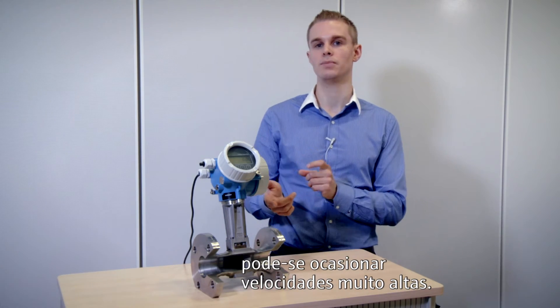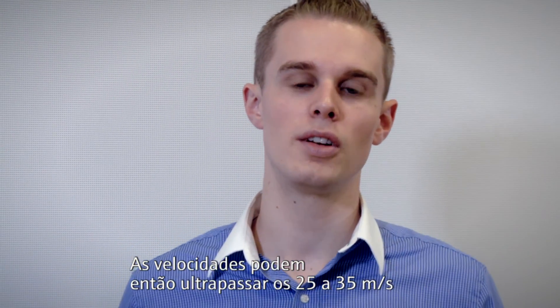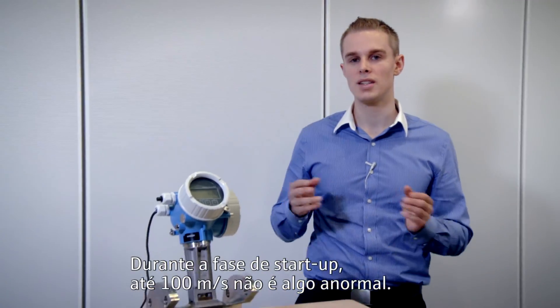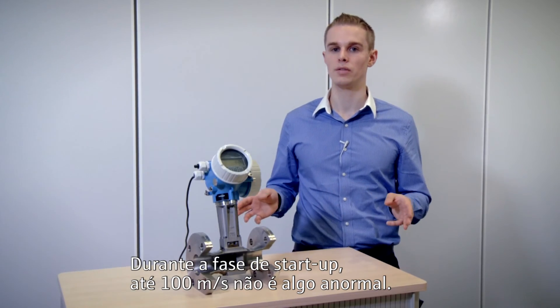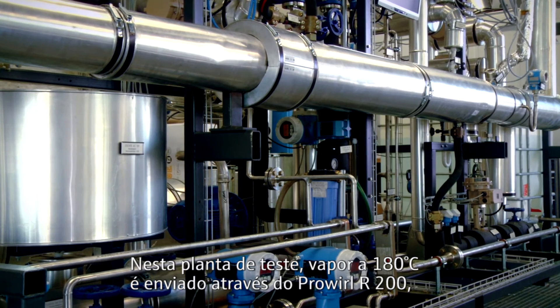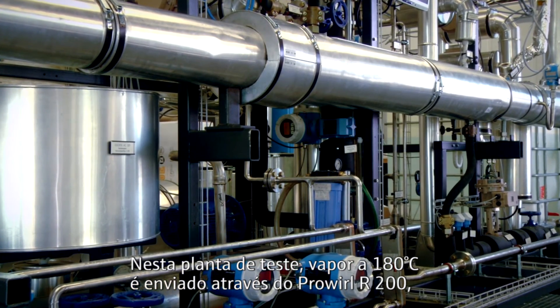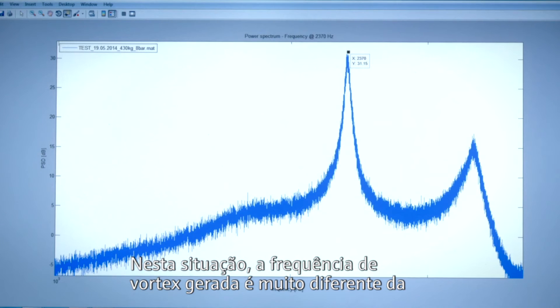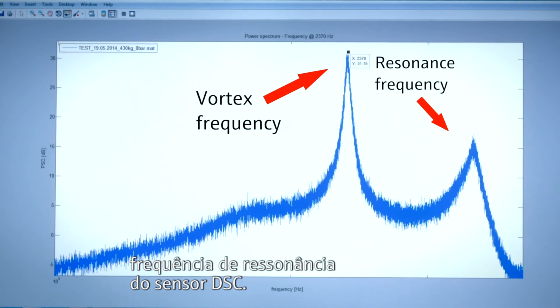Test 5 – Over-speeding. When a valve is opened abruptly, the velocities may exceed the 25 to 35 meters per second that steam lines are normally designed for. During the start-up phase, even 100 meters per second are not unheard of. In this test plant, 180 degrees Celsius steam is being sent through the Prowirl R 200, simulating typical steam flow conditions. In this situation, the vortex frequency is far different from the resonance frequency of the DSC sensor.